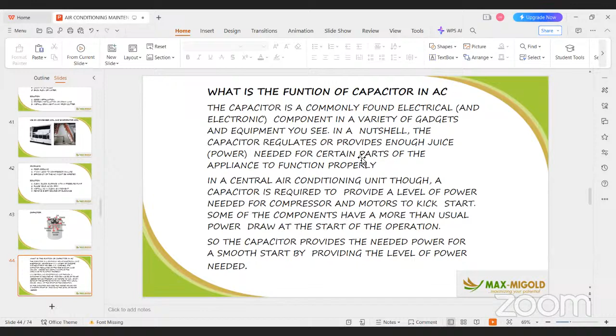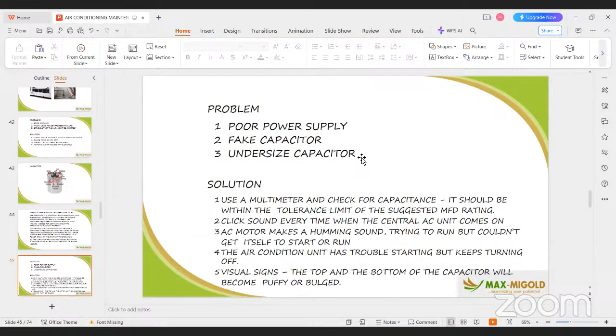So once they complain that the compressor has an issue, tell them to go and test the capacitor, whether the capacitor is the one that is faulty. Then you replace it. Then your AC will start working. Other problems are poor power supply and a fake capacitor on the side. So use the necessary power multimeter to measure and get the required power. Then ensure you use the right capacitor. Don't use an undersized capacitor for your unit.